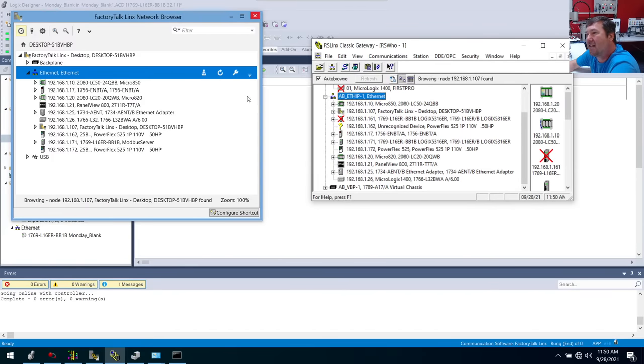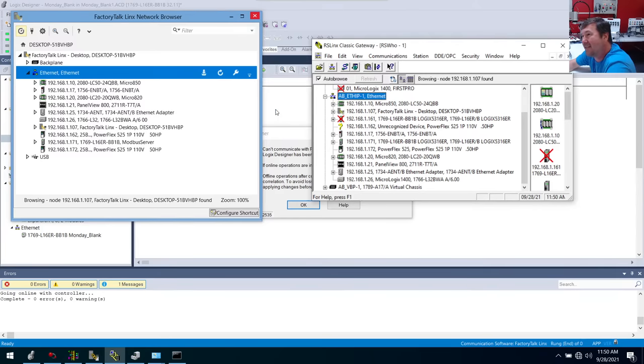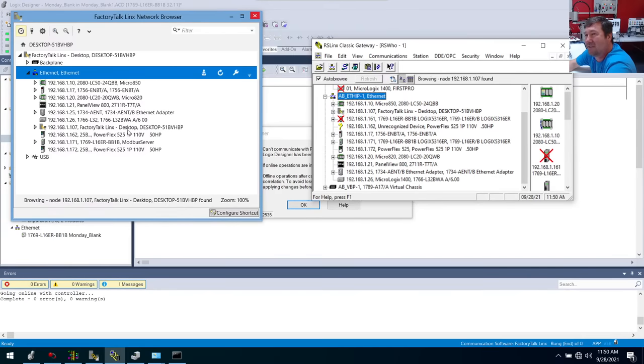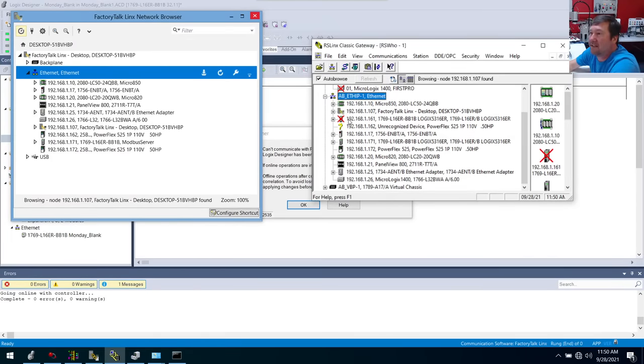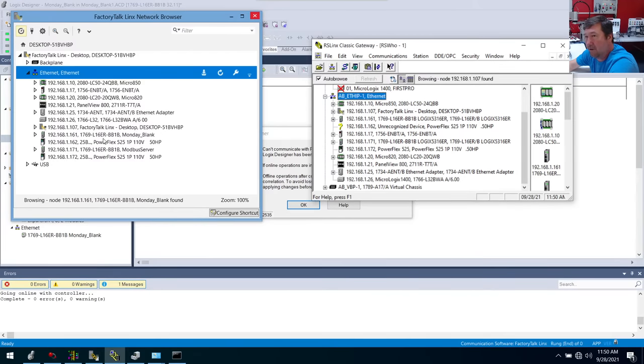This makes FactoryTalk Linx stay really clean and uncluttered. Because a lot of times I'll go and somebody will bring their PLC in, and they'll have 200 PLCs with a red X and they're trying to navigate all this to find the one. But in Factory Talk, I do know this was here at one time, and in RSLinx I don't. So I think this is something that just has to grow on me — or maybe there is a way to see the history. But that is the big difference to be aware of. So I'm going to plug both of those back in now. And you're going to see the red X go away over here, and you're going to see it reappear over here. In FactoryTalk Linx, they disappear when you're not communicating. In RSLinx Classic, they just become a red X.